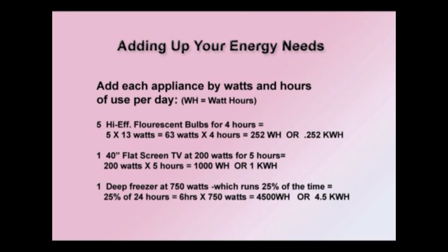And the last, a deep freezer at 750 watts, but it only runs about 25% of the time. The compressor only comes on about that amount of time per hour. So 25% of a 24-hour day is 6 hours, times the 750 watts it draws, equals 4,500 watt hours, or 4.5 kilowatt hours total. You can see how you could go around the house and add up exactly what your energy uses are going to be, and especially if you have a proposed setup for solar power, say in a cabin or a small house, you can put an energy budget together this way.